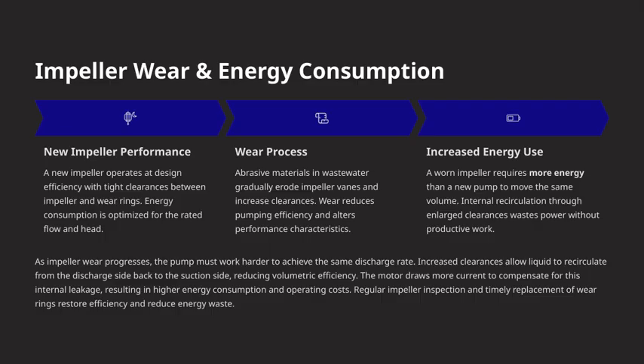As the impeller wears down, it requires more energy to move the same amount of fluid. This is because larger clearances allow some of the liquid to recirculate internally. Basically, the fluid leaks from the discharge back to the suction side. This internal recirculation wastes power and doesn't contribute to productive work. The more the impeller wears, the harder the pump has to work to maintain the same discharge rate. This increased clearance means more liquid recirculates inside the pump, which causes the motor to draw more current. That results in higher energy consumption and ultimately higher operating costs.